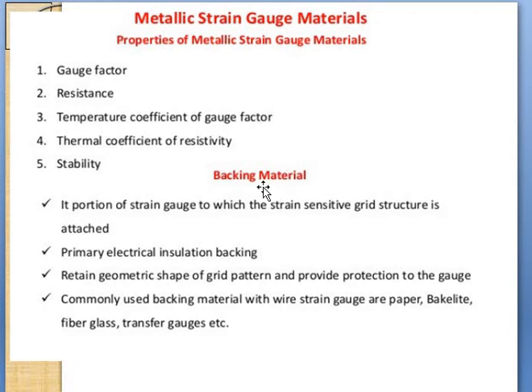The backing material is the portion of the strain gauge to which the strain-sensitive grid structure is attached. We need to attach the wire or foil to a carrier or backup. The backing provides primary electrical insulation and retains the geometric shape of the grid pattern, giving protection to the gauge. Commonly used backing materials include paper, bakelite, fiberglass, and transfer gauges.